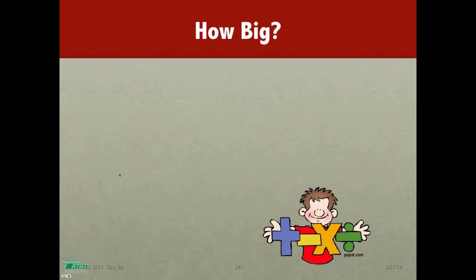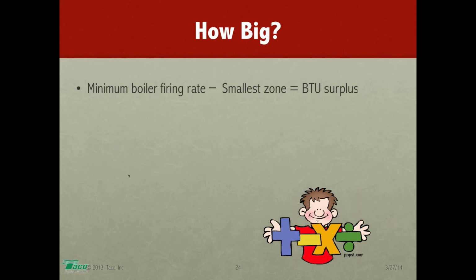Alrighty. Now, how big should the tank be? What size tank should we have? Well, here's the math. This goes back to your minimum boiler firing rate, which came up earlier. You want to find the minimum boiler firing rate, the lowest turn-down ratio of that boiler. If that minimum boiler firing rate is larger than the BTU load of the smallest zone, then you should go ahead and follow up with this. Even if it isn't, a buffer tank's not going to hurt you any. But here it's absolutely essential.